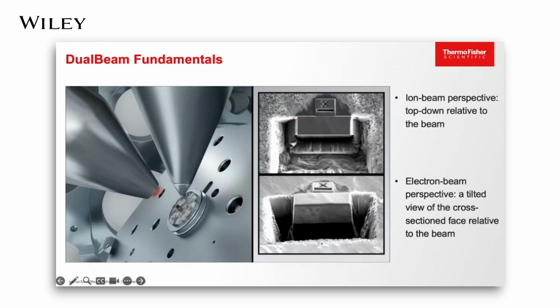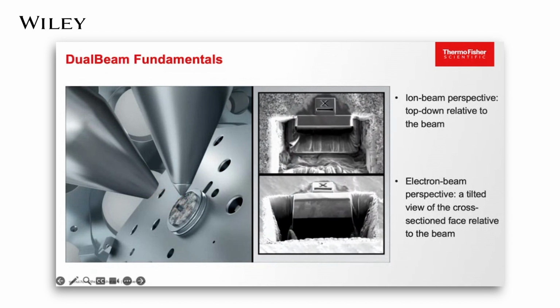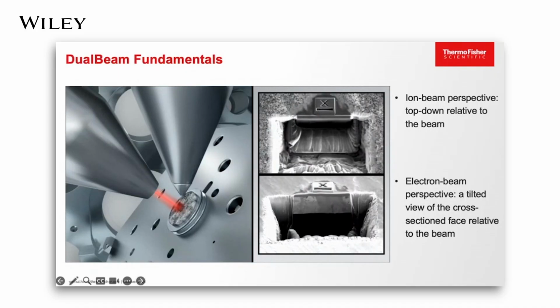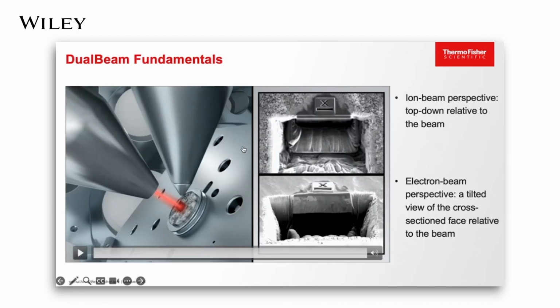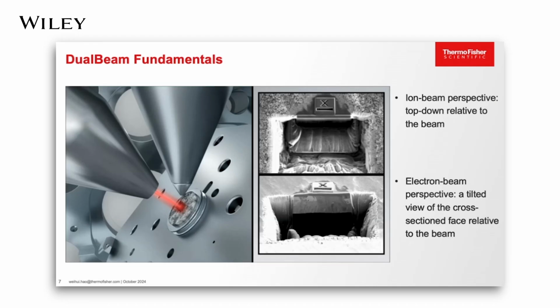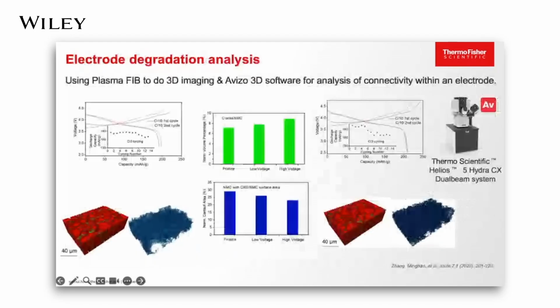Here, we introduce our dual beam technique. If we go into the microscope, we can observe the sample with SEM. Then the red beam we can see is actually cutting away materials and sputtering away materials with focused ion beam. In this particular example, we are able to take all these images and make a 3D rendering or do 3D reconstruction of that sample. But if we just want to expose one section of the sample site specifically, a dual beam does that quite well. This shows how it's done.